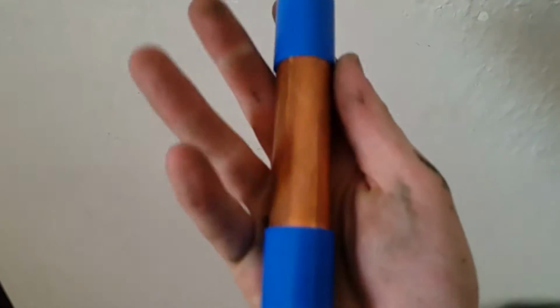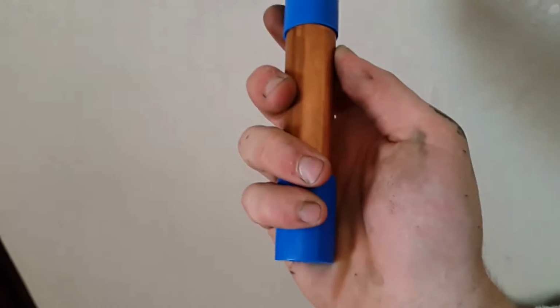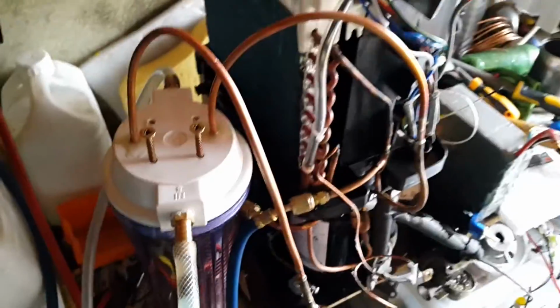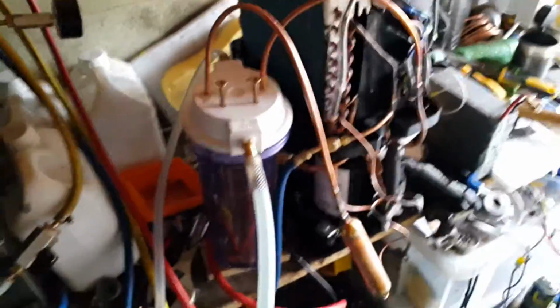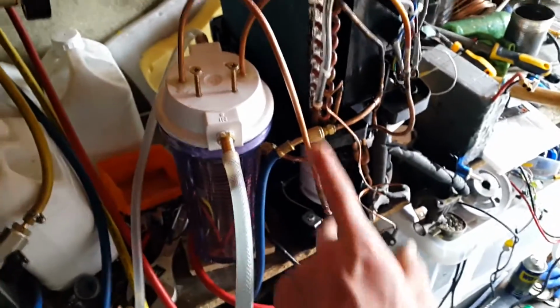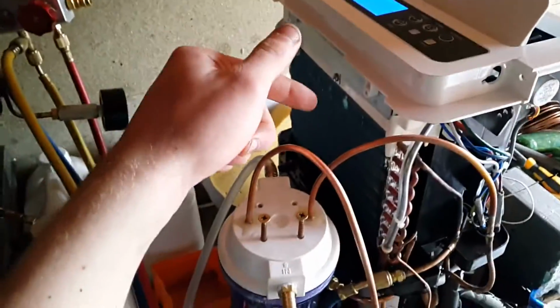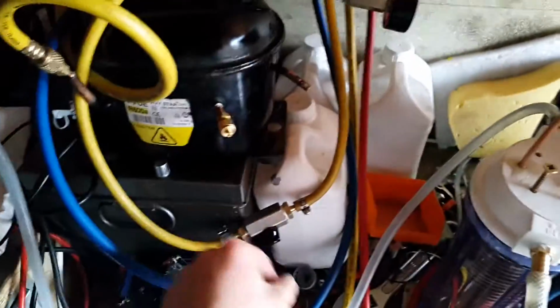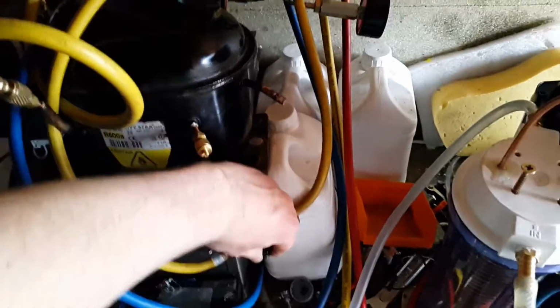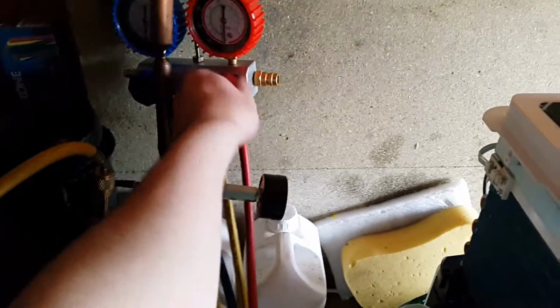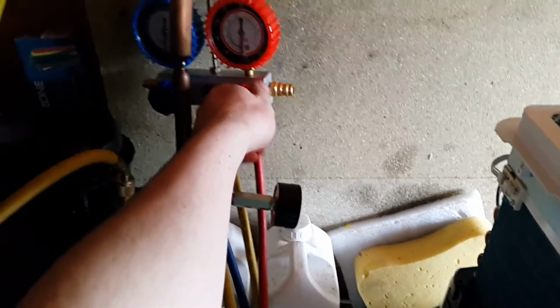So this is a filter dryer I got. It's 30 grams and it was quite a bit bigger than I was expecting it to be, but I should still have space for it. Okay, now I'm at the stage where I've got water flowing through the new condenser, and I'm just putting the thing under vacuum just now, and I'll then close off the high side and start putting in the refrigerant. The amount to put in is liquid.